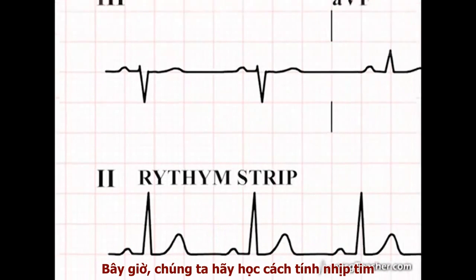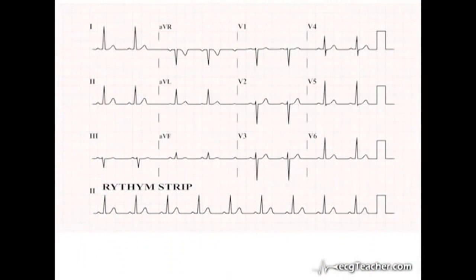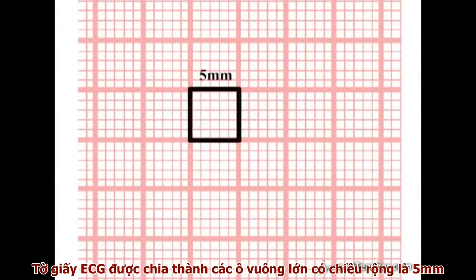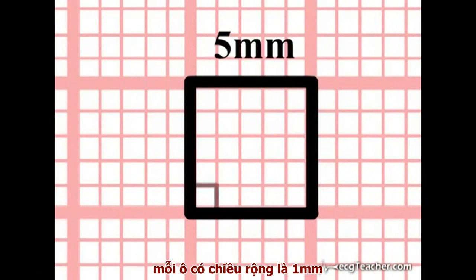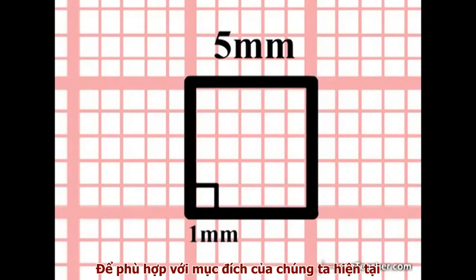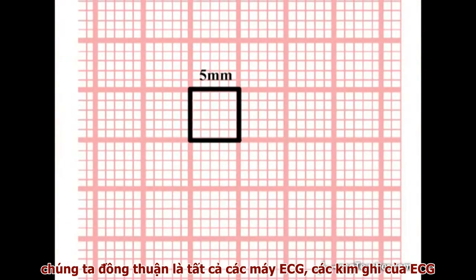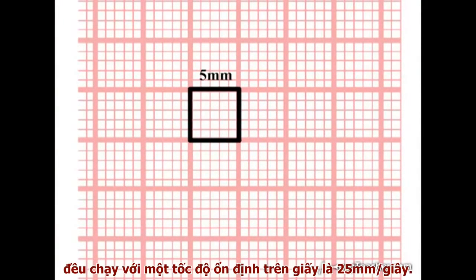For now, let's deal with the calculation of heart rate. ECG recording paper is divided into large squares 5mm wide. These large squares are in turn further subdivided into small squares, each of 1mm in width. In all ECG machines, the recording needles run at a constant speed over the ECG paper of 25mm per second.